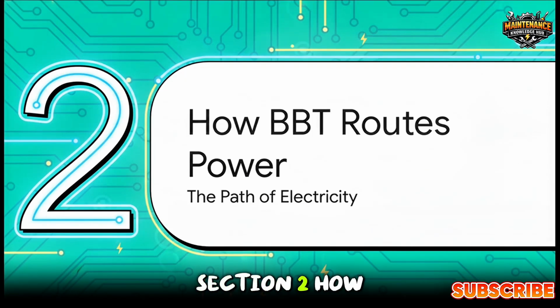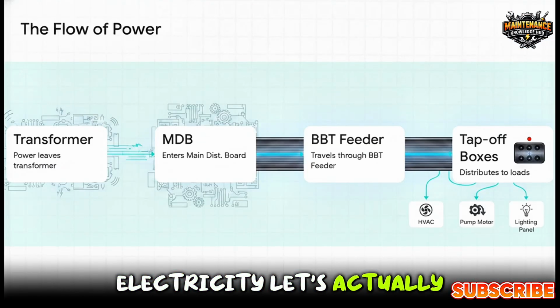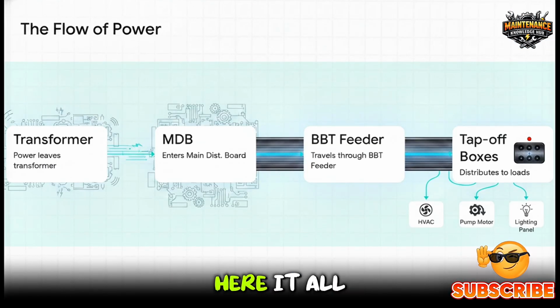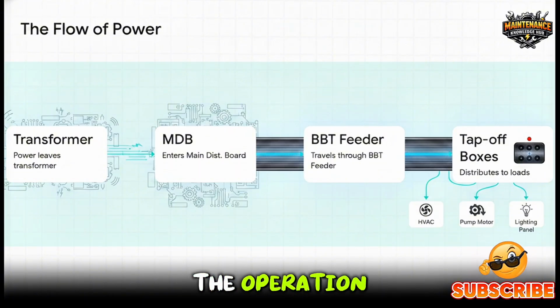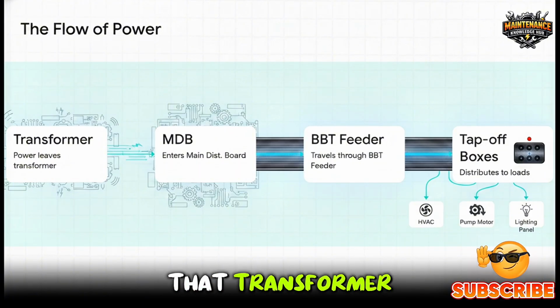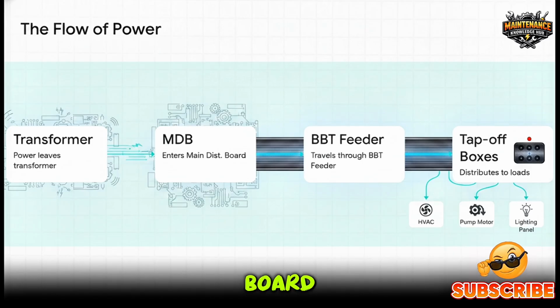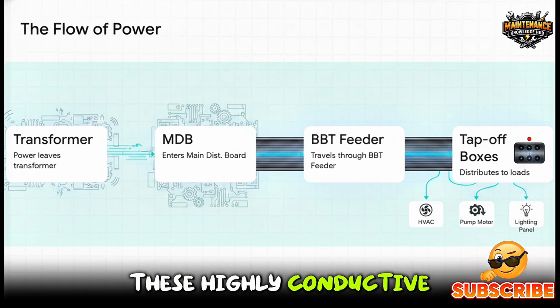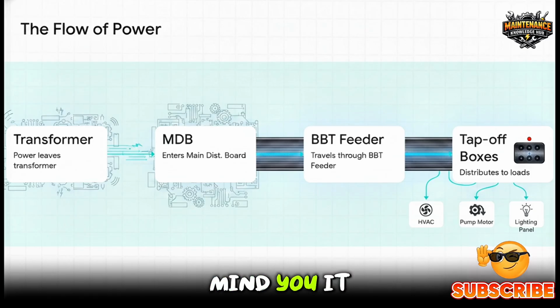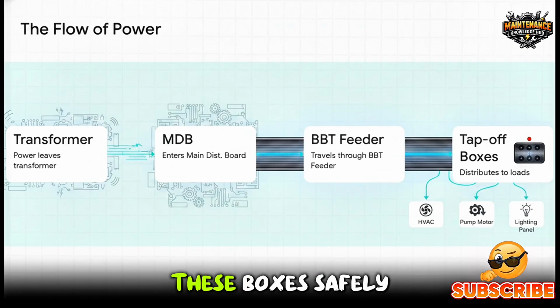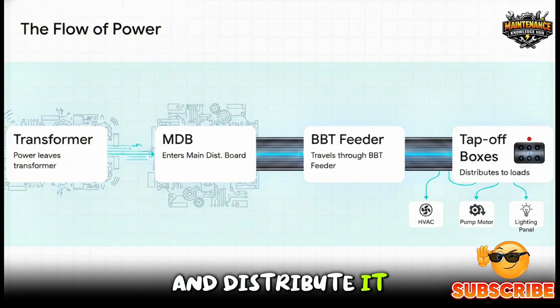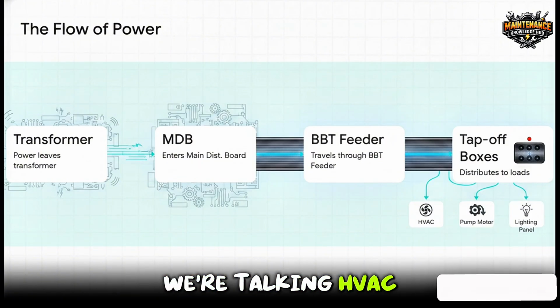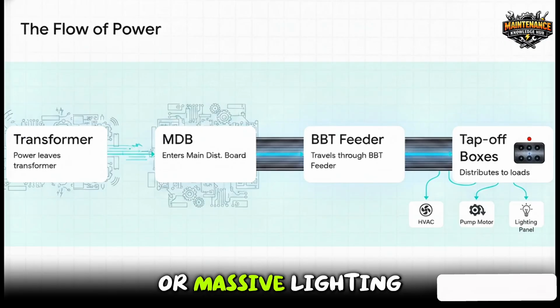Let's move to Section 2, how BBT routes power, the path of electricity. Let's actually trace the step-by-step journey of the electricity here. It all begins at the real heart of the operation, the transformer. The raw power leaves that transformer and immediately enters the main distribution board, or MDB. From the MDB, the power is fed directly into the heavy-duty BBT feeder. As the current races down these highly conductive bus bars, with almost zero resistance, mind you, it reaches the plug-in tap-off boxes. These boxes safely pull the power from the main line and distribute it right to the specific electrical loads. We're talking HVAC systems, heavy pump motors, or massive lighting panels.